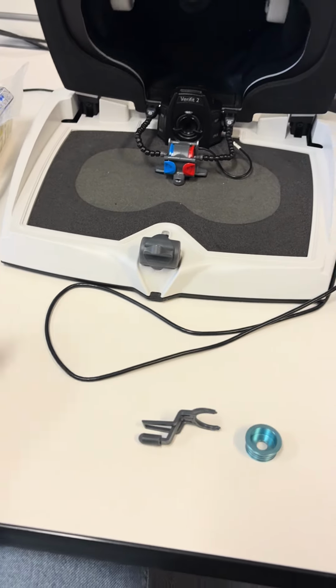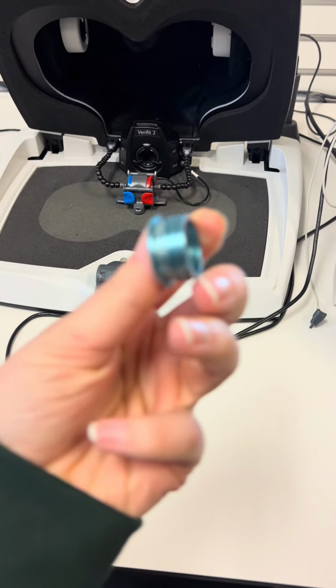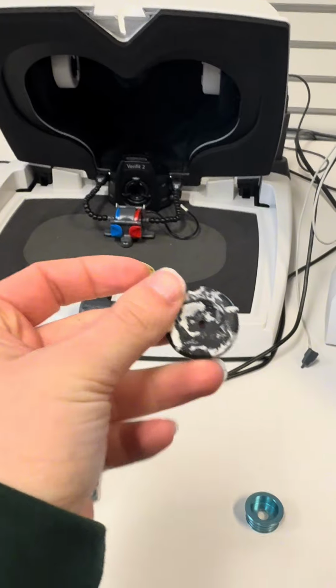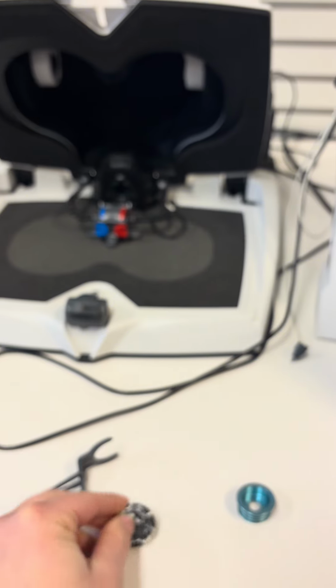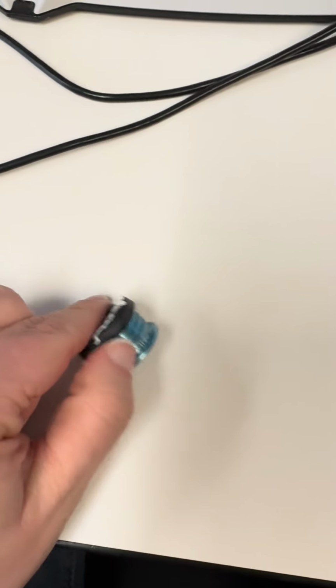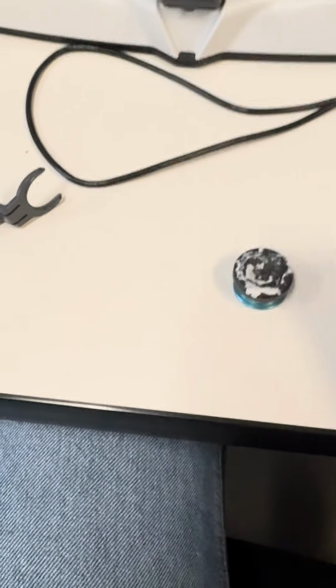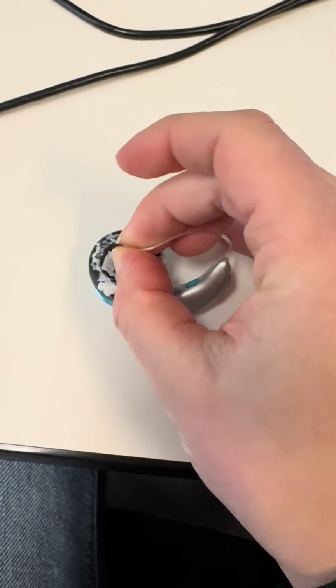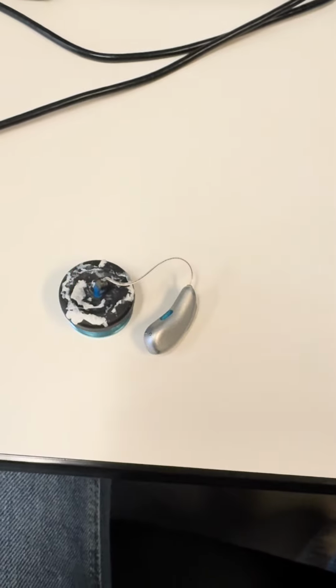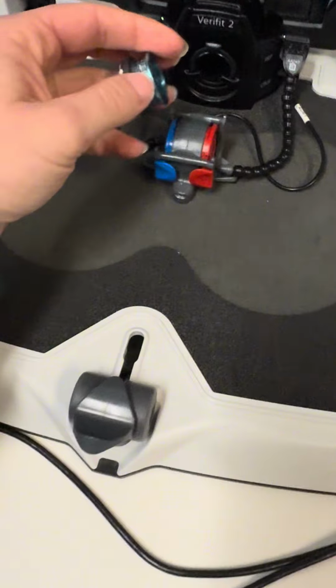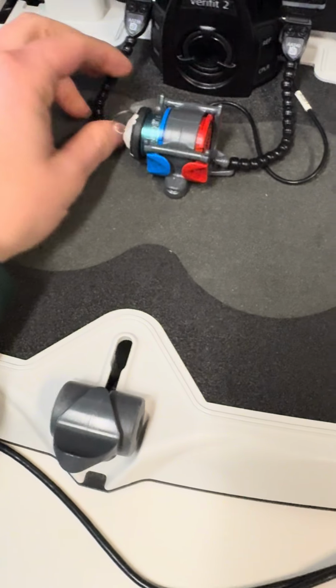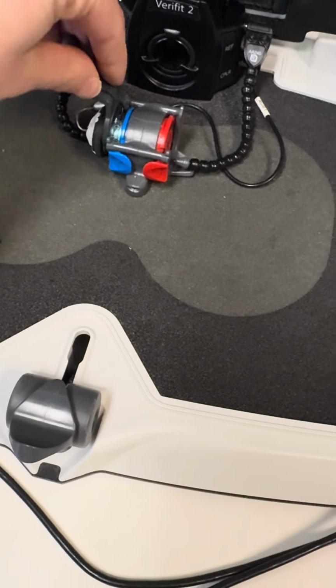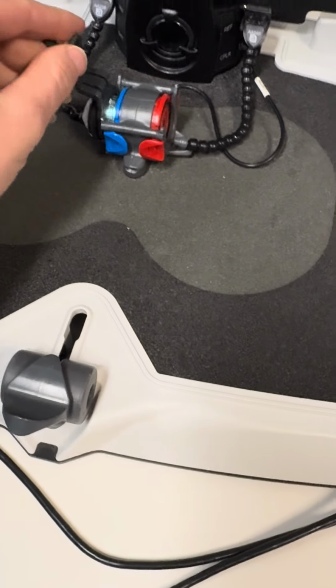To set the hearing aid up in the test box, we need this blue coupler, which says ANSI on it. ANSI. And the little cover for a RIC. This one's pretty dirty, but it will do the trick. And this if you want a clean setup. Okay, so we are going to attach this to the blue coupler. And then we are going to take our receiver and make sure the speaker is right flush with the opening and wrap putty around it so it stays stable. Finished product should look like that. And then we are just going to slide it in the blue side and use this holder to kind of set the hearing aid up in there.